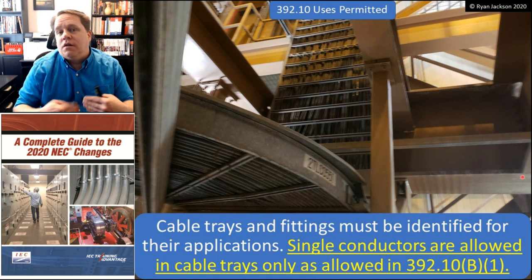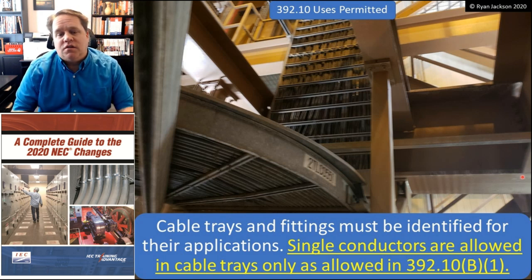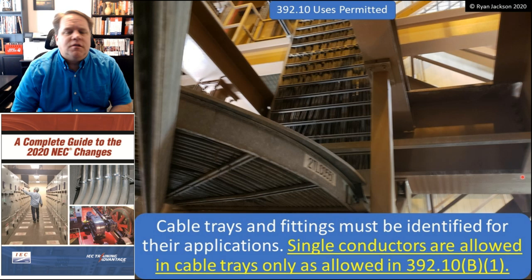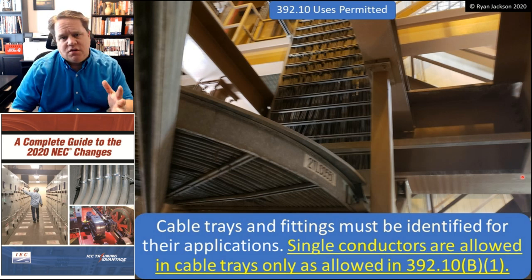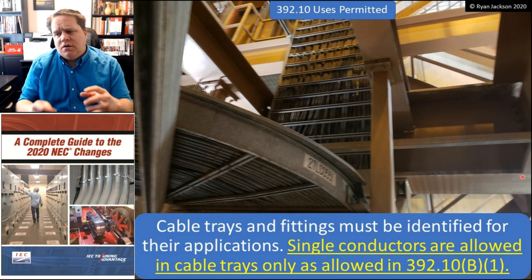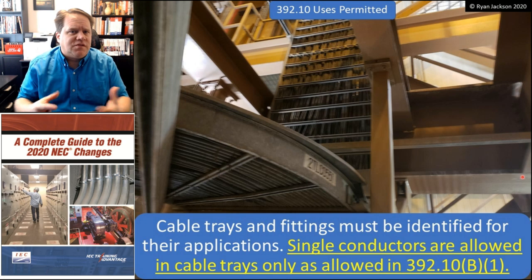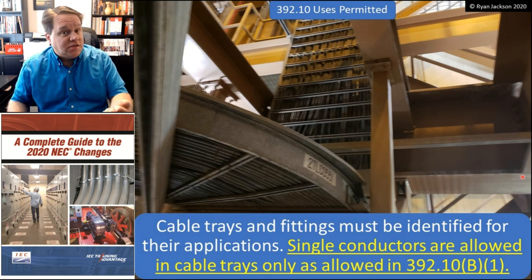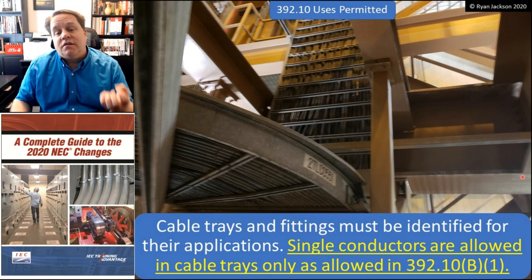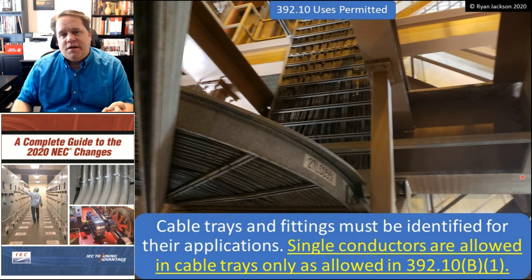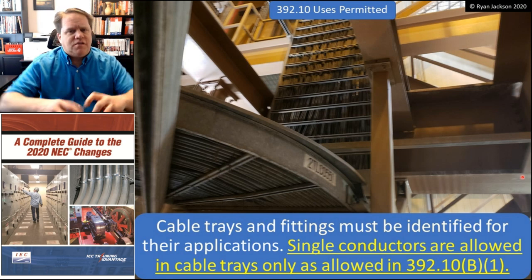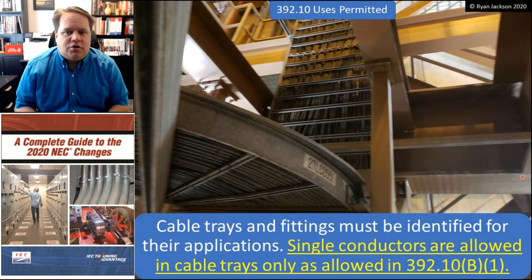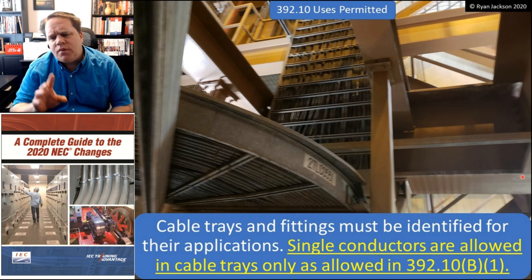392.10 also gives a nice little allowance. First of all, cable trays and fittings have to be identified for the application — you can't just string a bunch of stuff together and call it a cable tray. It doesn't necessarily have to be listed, but it does have to be identified for the application, meaning it's designed as a tray and designed for use as a tray.